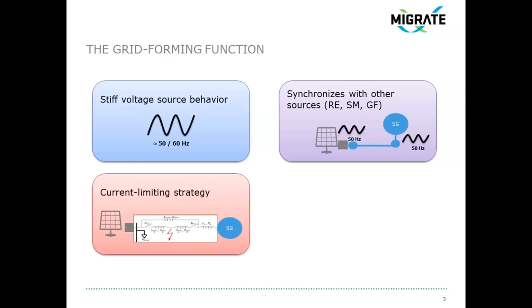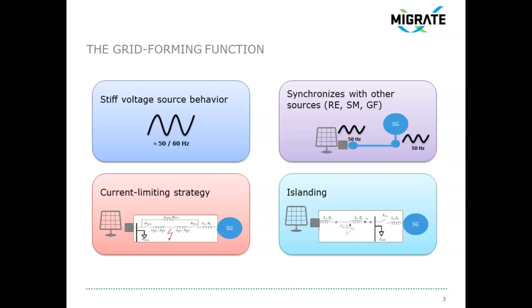You also need to provide current during a fault, but as grid forming is provided by inverters that have a very limited overcurrent capability, you need a smart current limiting strategy to avoid jeopardizing system stability as soon as you reach your maximum current. And of course, you need to be able to handle islanding, at least for a few seconds, to leave time for other mechanisms to come into play.